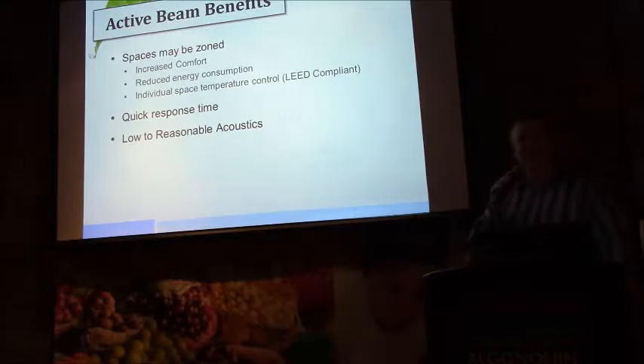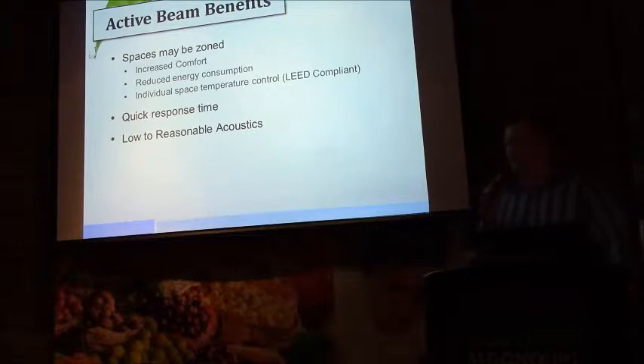It was understanding that that piece of equipment was selected specifically to address not just the thermal comfort of the space, but also the air distribution in the room to limit the air velocities, as well as deal with the acoustic content and the radiant asymmetry of the glazing that was chosen for the space. That's really what drove the selection.